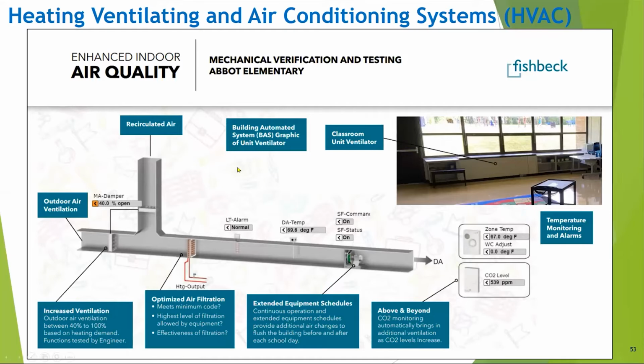This image of the sort of this T-shaped gray image is out of our building automation system. We have these graphical representations in our building automation system. This is an engineering representation of this unit ventilator, which is a very common piece of equipment in many of our buildings. It has an outside damper that lets outside air in. In this graphic, you see where the outside air is coming in. Here's the damper and a second damper. Then you have the recirculated air. They mix at some percentage and they move across a filter medium, are pulled through by a fan, and then you have your discharge air going back into the space.